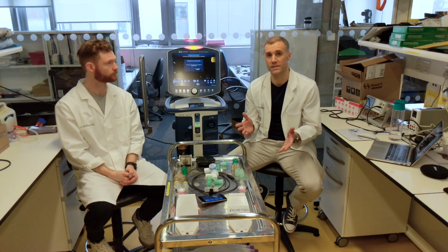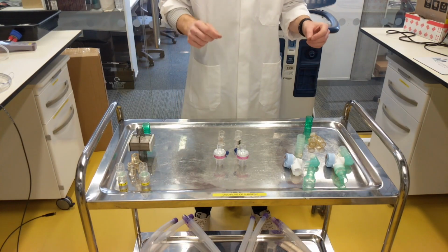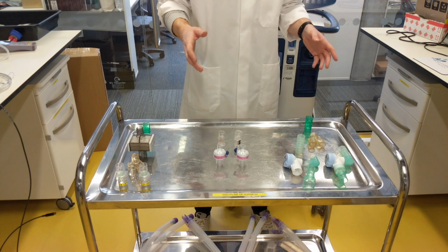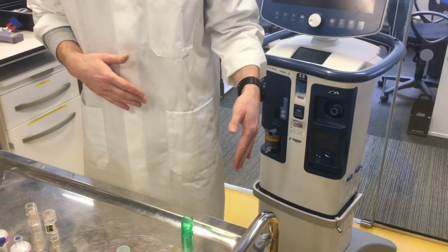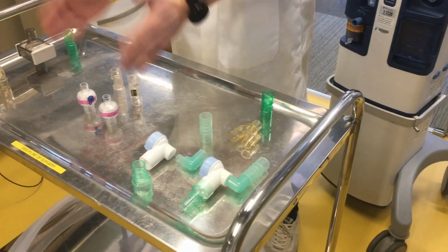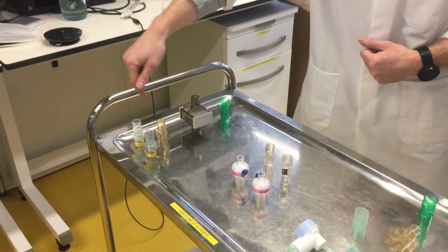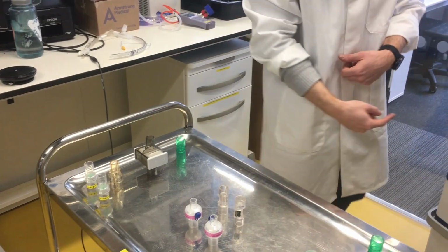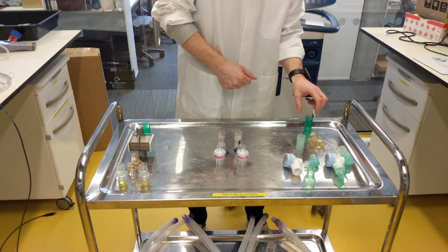So, onto the system. What I'm going to do here is run through the different components in the system and the assembly. The way that we're laid out is we have, coming from the ventilator on the right side, the inspiratory line, coming back to the patient level components in the center, and then coming back through the expiratory line to the left hand side of the ventilator here. So I'll go through these components and assemble them one by one.